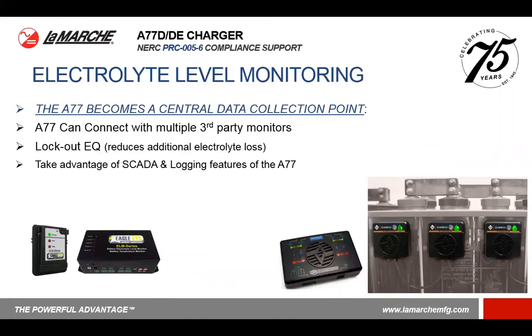By integrating the electrolyte monitoring with the A77, we can have smart features, such as locking out the equalize, and this can reduce additional electrolyte loss. The electrolyte level monitors by themselves typically have dry form C contacts that could be monitored at an RTU, but by including it in the A77, you gain additional features and intelligence in your DC system.